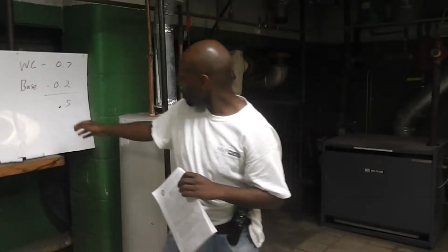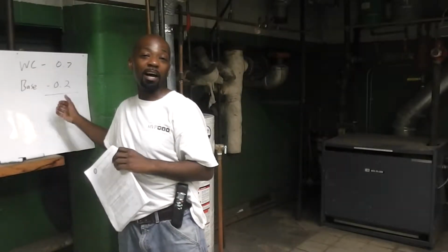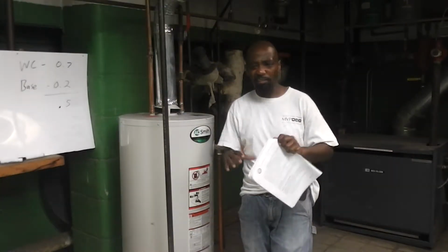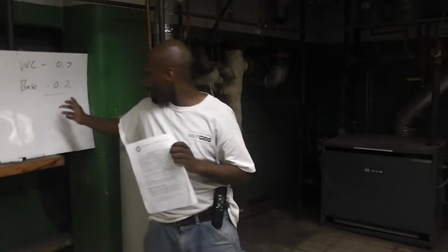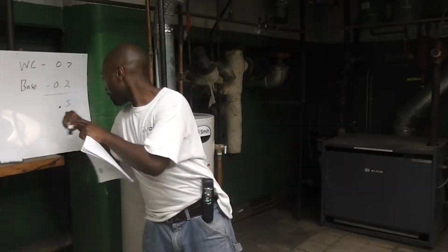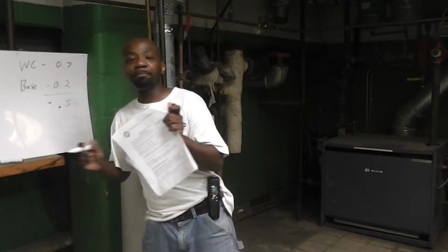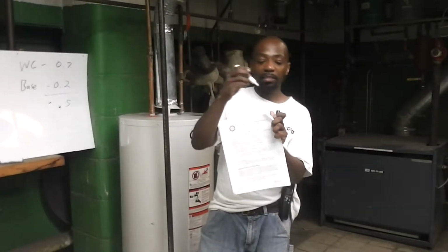When we ran our test, it looks like we got -0.5. So we're actually in good standing. We passed the worst case scenario, so we can continue with the rest of our tests under the worst case. We got -3 as the limit. We got, and I should put here it's a negative number of course, -0.5. So we're still good. We're nowhere near -3 pascals.